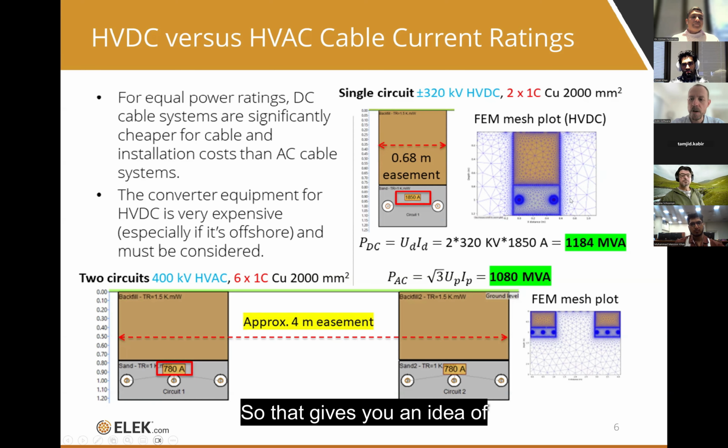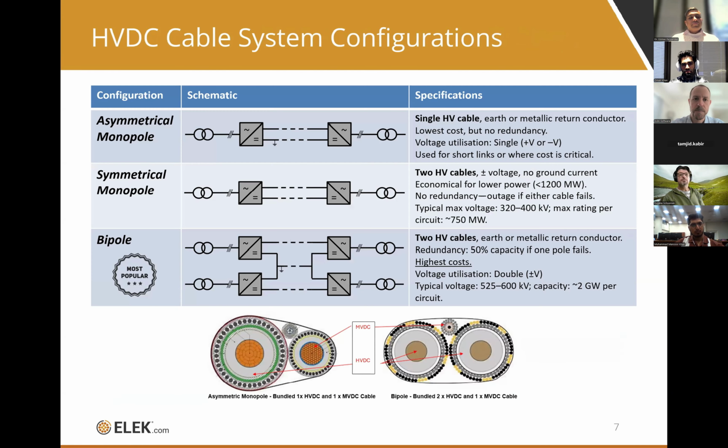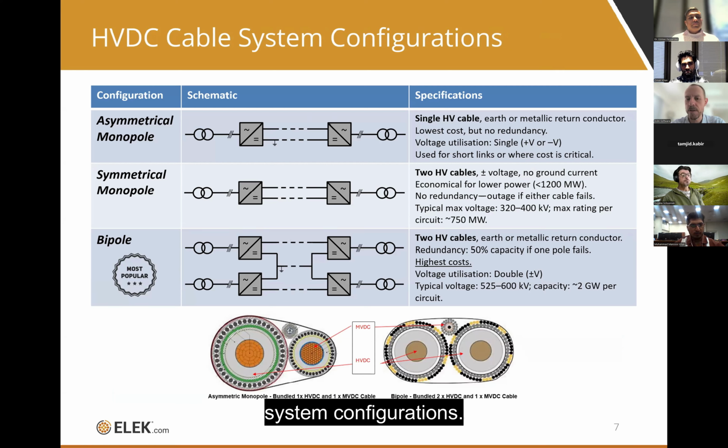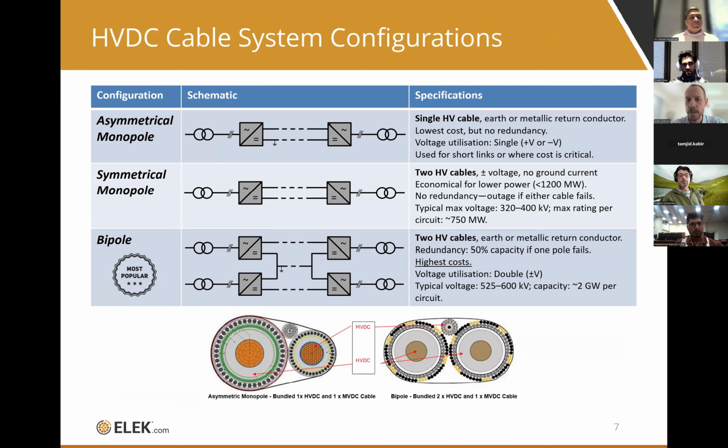So that gives you an idea of why HVDC power delivery is so attractive, HVDC cable. Let's talk about the different HVDC cable system configurations. So we've got the asymmetrical monopole, the symmetrical monopole, and the bipole system.